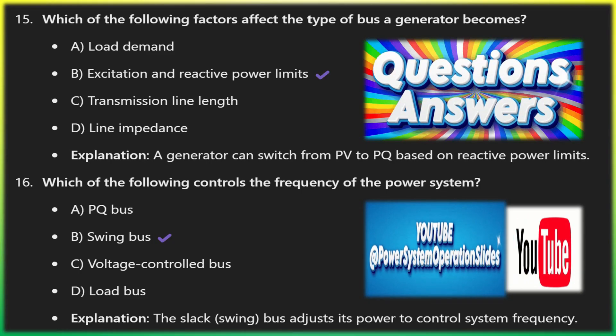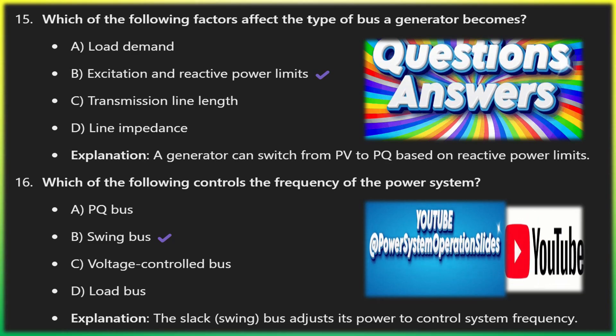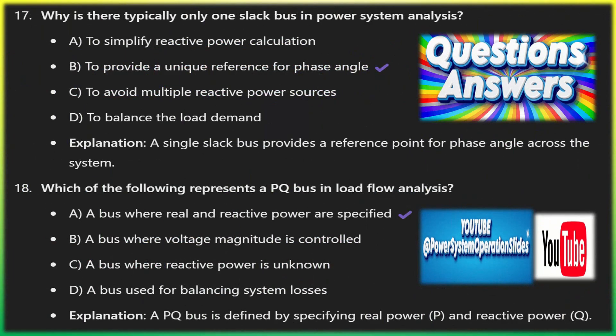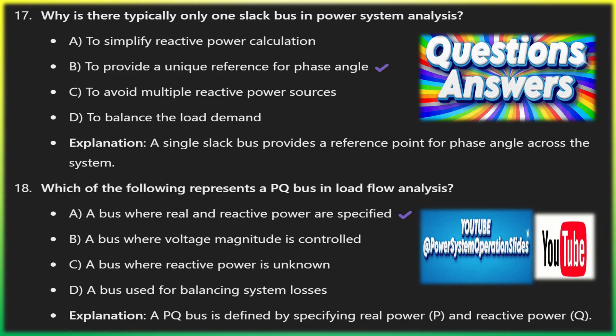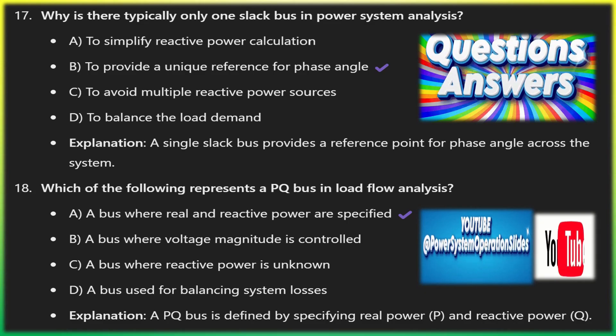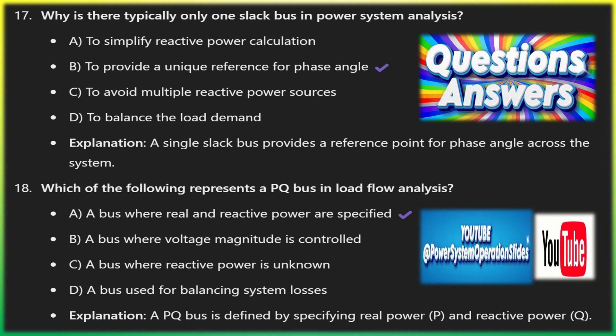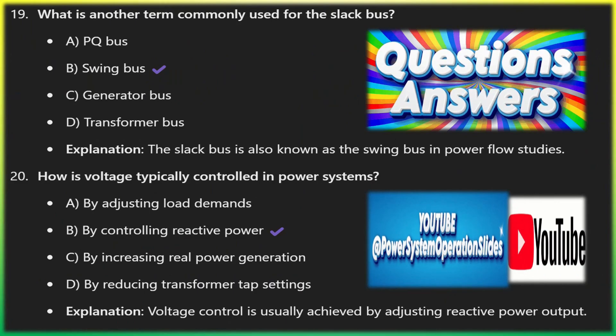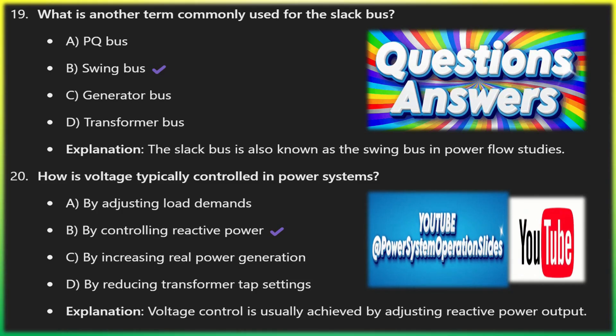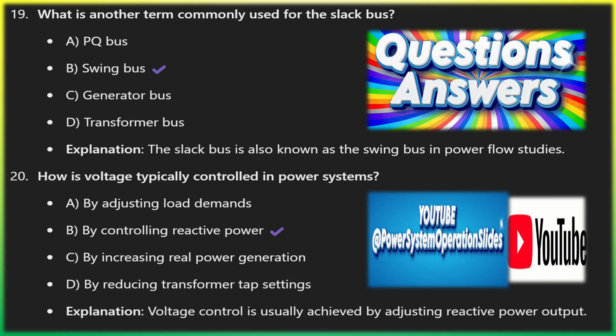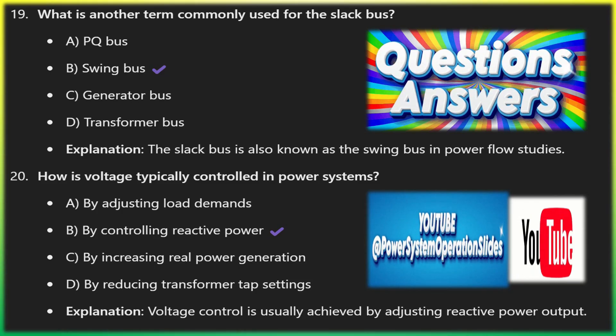Reactive power control and bus type transitions: under over-voltage conditions, if a bus experiences significant deviations in voltage, it can affect the type of bus it is classified as. For example, if a generator bus (PV) is unable to maintain its voltage due to exceeding its reactive power limits, it may temporarily operate as a PQ bus. Capacitor banks and SVCs: capacitor banks or static VAR compensators (SVCs) are often installed at buses to help manage reactive power more locally.